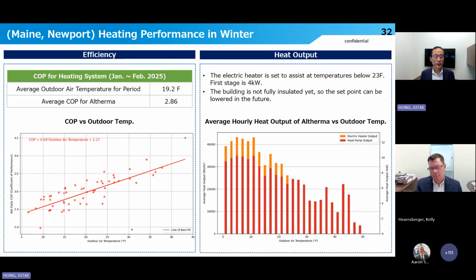Then, how about the COP and heat up time in winter? The average heating COP was 2.86 during January and February this year at 19.2 average outdoor air temperature. Also, when we check the heat output from the unit, around 85 to 90% of heating was produced by the heat pump and 10 to 15% by booster heater. This building is not fully insulated yet, so we expect the heating by booster heater will be lowered next winter.